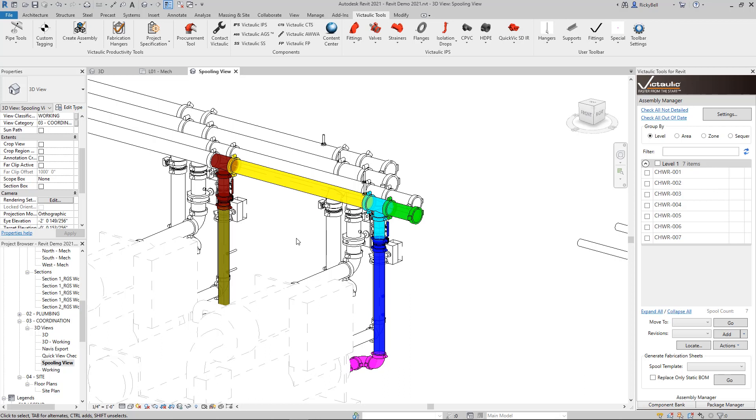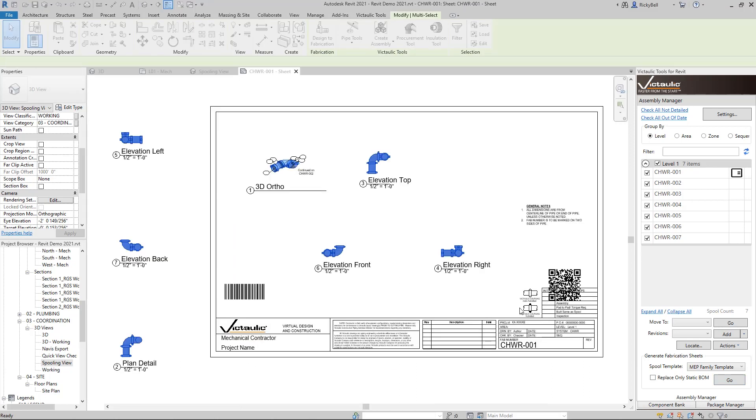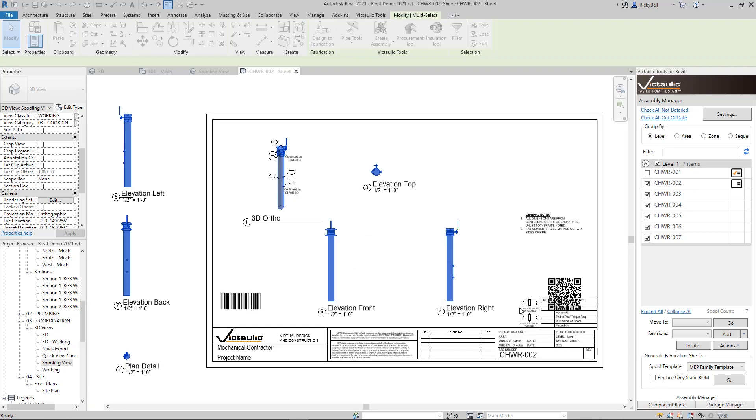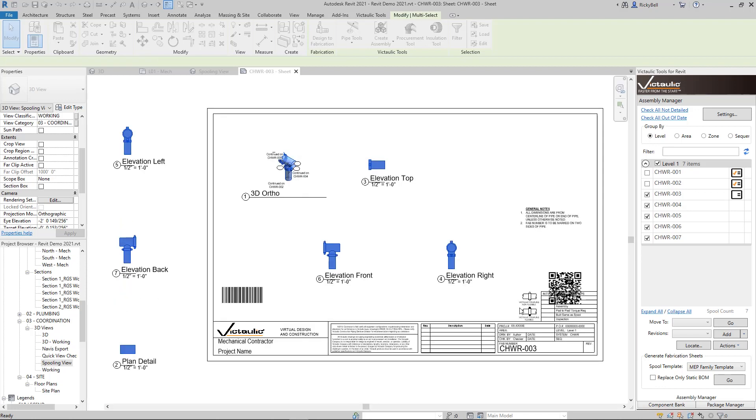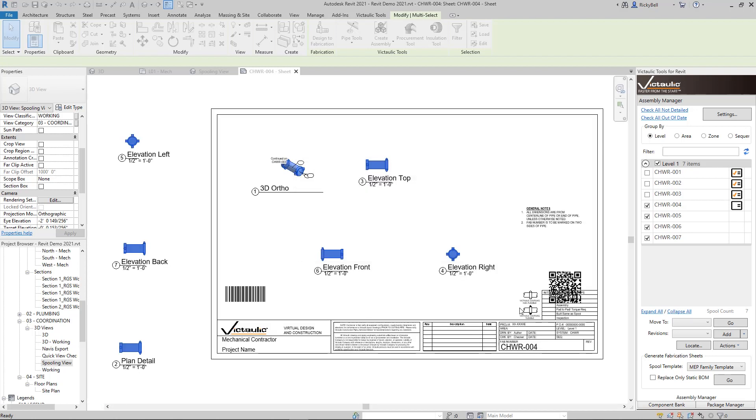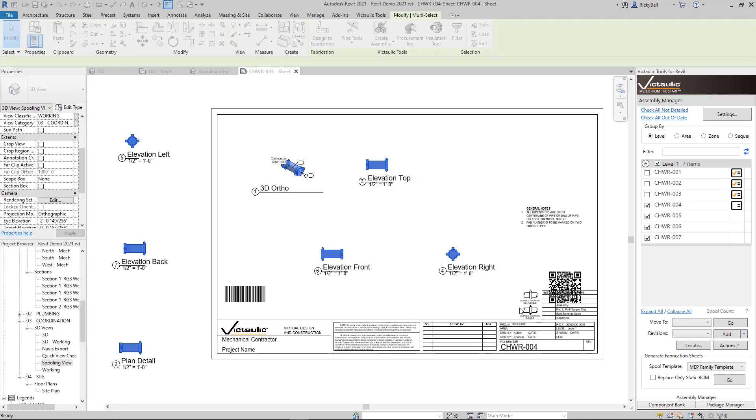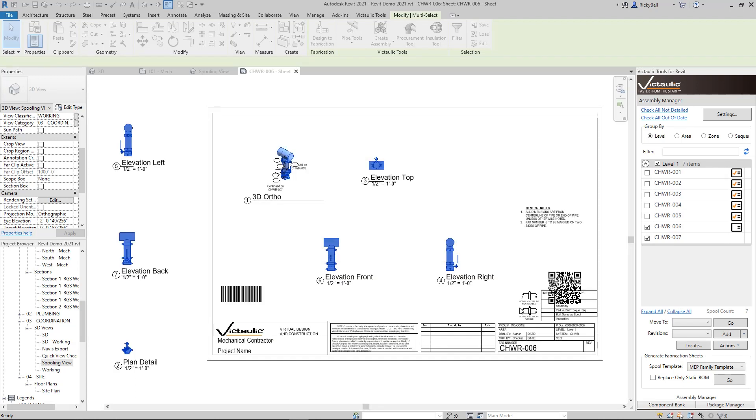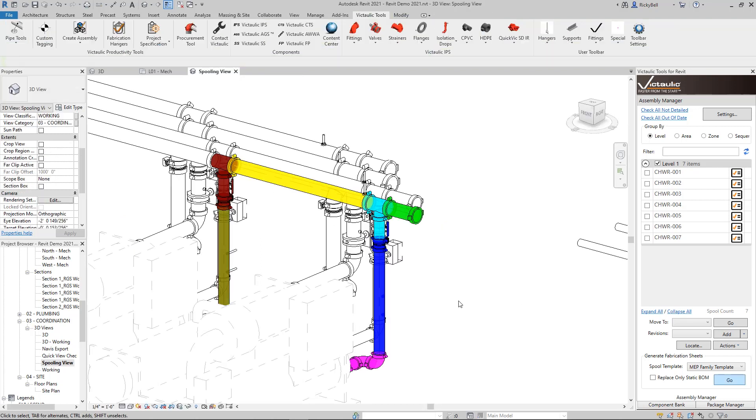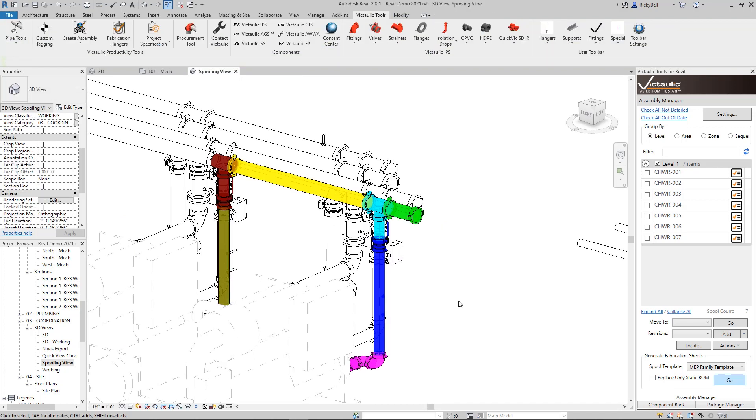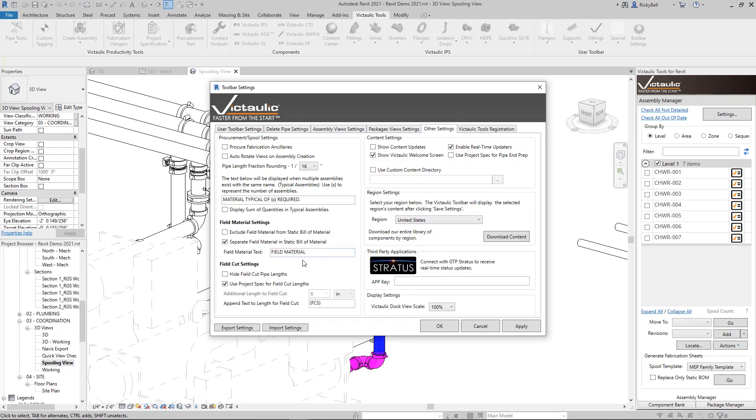So I just did a few here and I'm going to detail these as well using the Assembly Manager. In previous versions of Victaulic Tools for Revit to handle field cut lengths was more of a global setting. So under Toolbar Settings and the Other Settings tab, down here in the bottom left-hand corner, you'll find that previously the additional length to field cut could be set as 6 inches or whatever you specify. We want to get a little bit more precise with this. So by checking Use Project Spec for Field Cut Lengths right here, it's going to refer back to the database of information that we just set up.